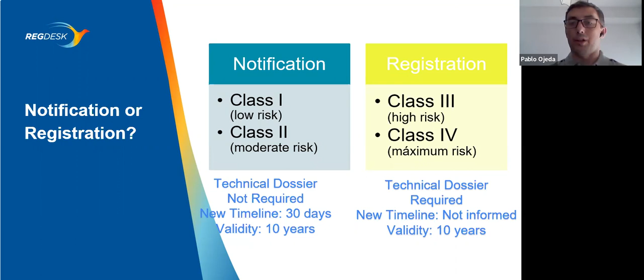The notification for class 1 and class 2 is a process that was in place many years ago. There is a regulation from 2015, and now it's here in one place. And the requirements: there's no need to present the technical dossier, but having one is required, just not presenting it to the agency. The regulation established a timeline of 30 days to review the technical file. Nothing was said about the new timeline for the technical dossier for class 3 and 4, but it's going to be defined in a further decree when this regulation is implemented. The validity of the registration and notification for both is 10 years. This is the same.